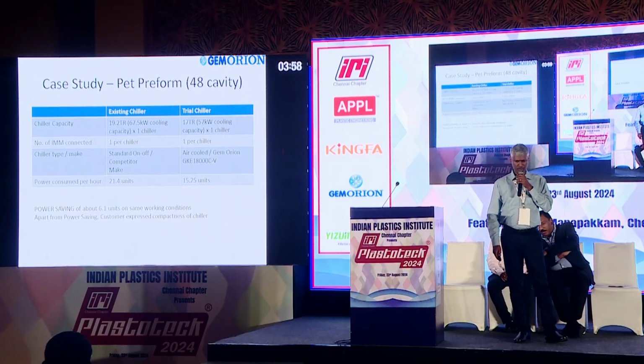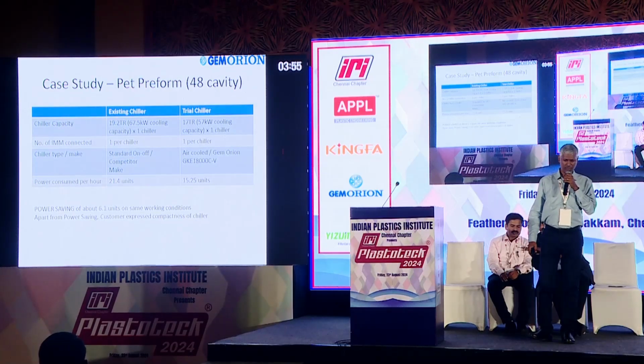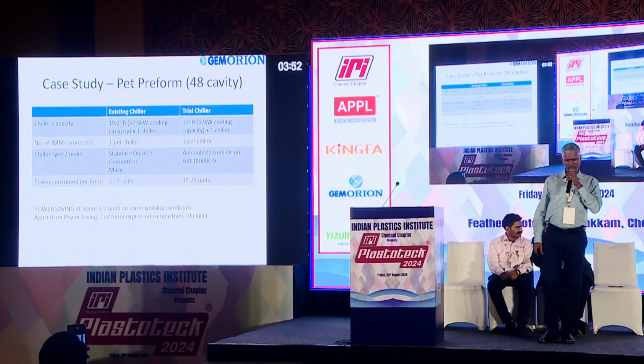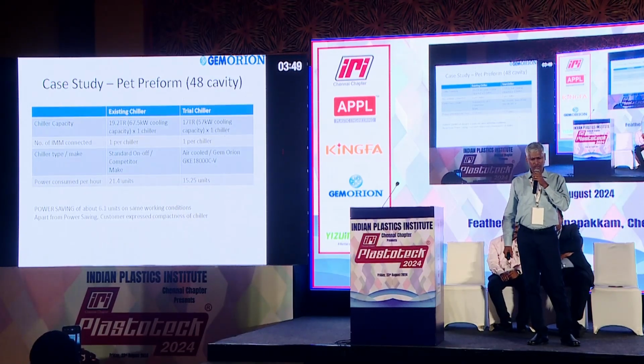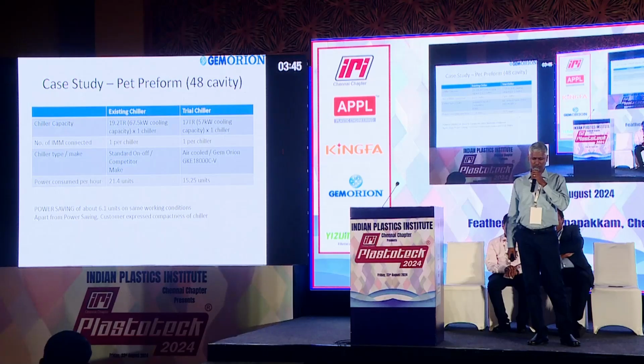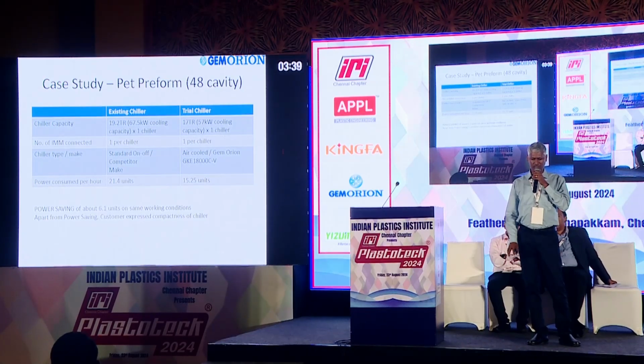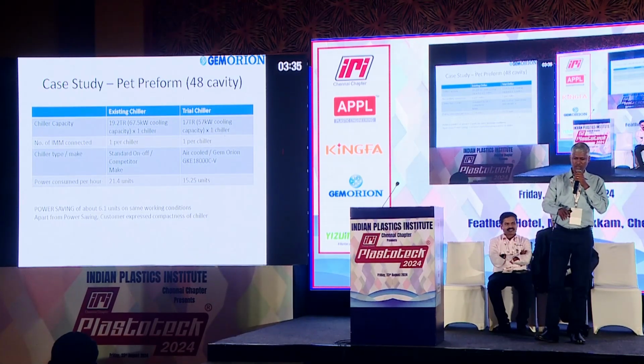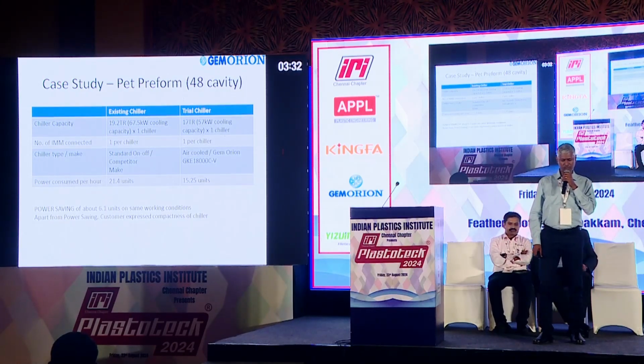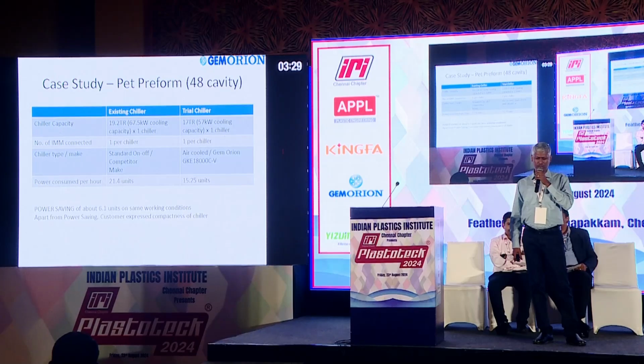Okay, a few case studies. This is for the preform industry, for a 48 cavity preform. The machine was a 250 ton machine, with 19.5 gram shot weight and about 19 or 20 second cycle time. There was a competitor chiller with that customer, consuming around 21.4 units per hour. This data is based on 24-hour power study. In the same place we gave our inverter chiller, which is consuming around 15.25 units. Probably you can say the competitor chiller is big and our chiller is smaller.